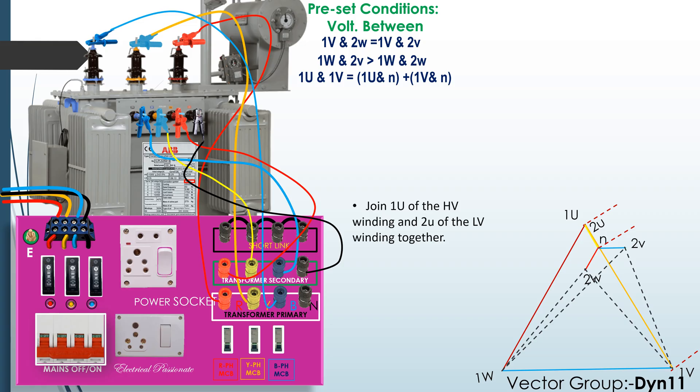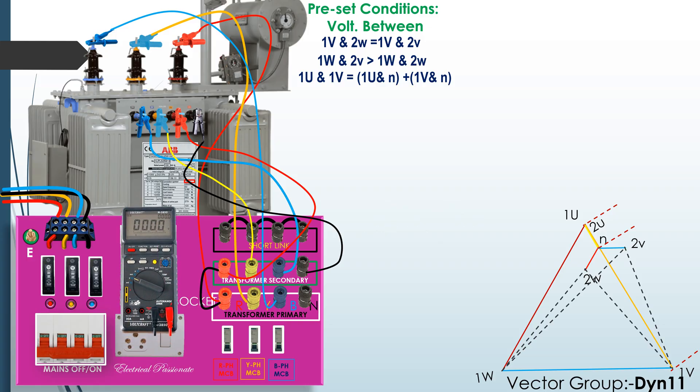Join 1U of HV winding and 2U of LV winding together at testing board. Apply 400V supply to HV terminals. Measure the voltages and record these in a table.